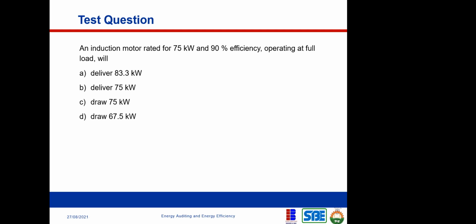So let me not waste so much time on this. The answer is actually that it is going to deliver 75 kilowatts. That is B. Now the thing is this: this 75 kilowatt is the rated output of this motor. And this 75 kilowatt rated output is when the motor is operating at 90% efficiency, right? And they told us that this motor is now operating at full load, right? So everything is optimum. Since everything is optimum, it is actually going to give out the rated output, which is 75 kilowatts mechanical.